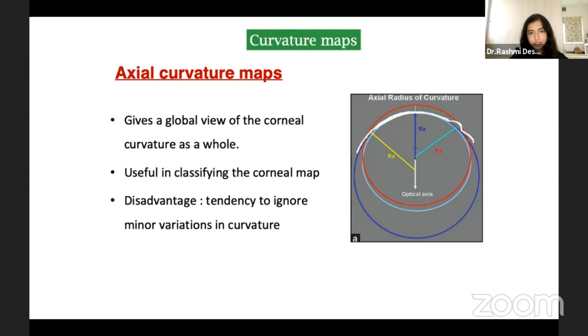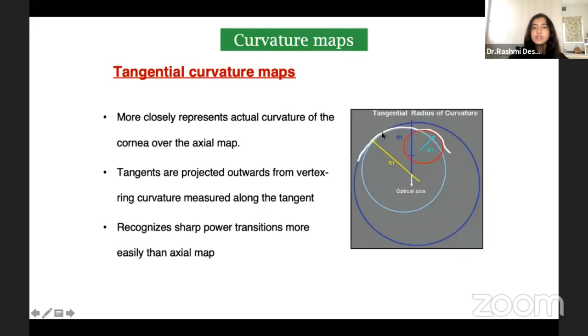And the disadvantage is that it has a tendency to ignore minor variations in the corneal curvature, which are given by tangential curvature maps. Because in tangential curvature maps, there are tangents which are projected outwards from the vertex, with ring curvature measured along the tangent. And if you look at this particular cornea, you are getting a different radius of curvature here as compared to the one here, as compared to other points. So you're getting a radius of curvature which is accurately measured at each point. And that is the advantage of the tangential curvature map.